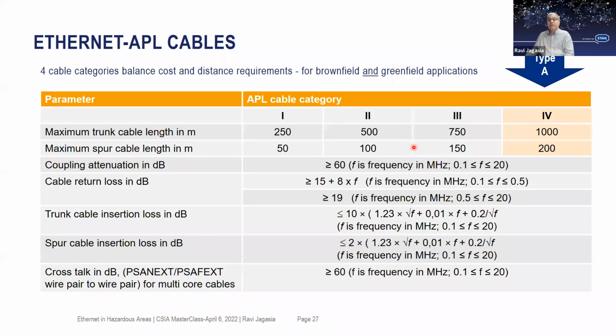And more specifically, the cables specified under the 61158-2, the type cable 4, which is what is classified as type A, allows you to run the cable length to about 1000 meters with a SPUR at around 200 meters. We will not go into all this, but just to share with you that if you are doing other cables, and this could be a challenge when you would want to migrate at a low cost, that you use some of the current cables in your plant and your customer asks you to use them, you could be affecting the maximum distance you can travel.